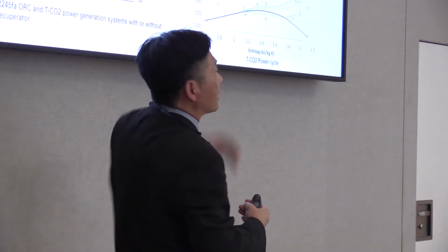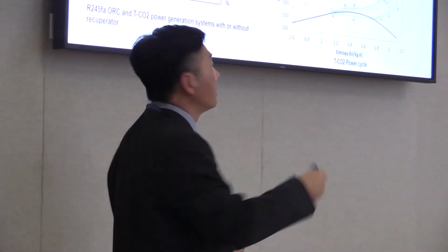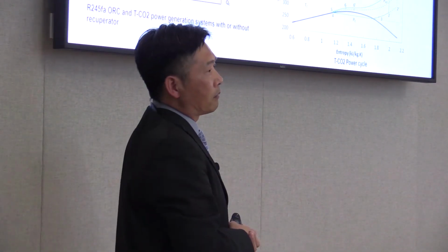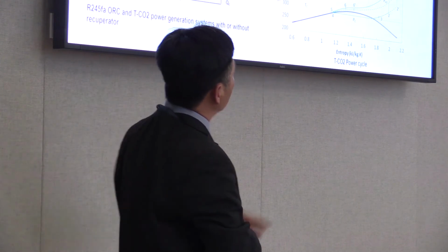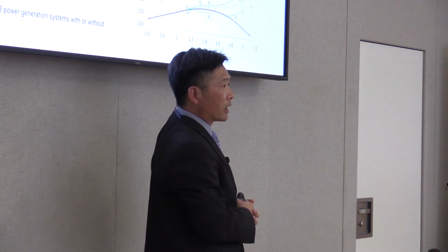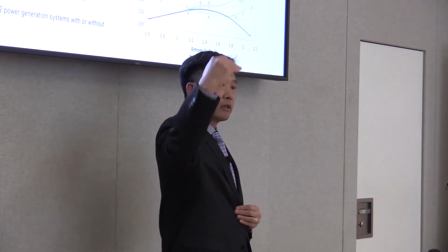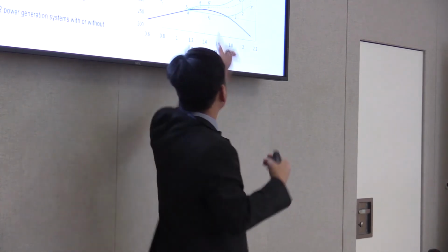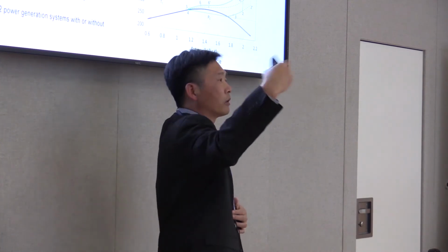So we assume the heat sink temperature is about 20 degrees C, so we can determine the low side pressure, PC, for both cycles. And this is for the CO2 transcritical cycle. There's no limitation for the high side pressure, because it is transcritical, it's above the critical pressure.